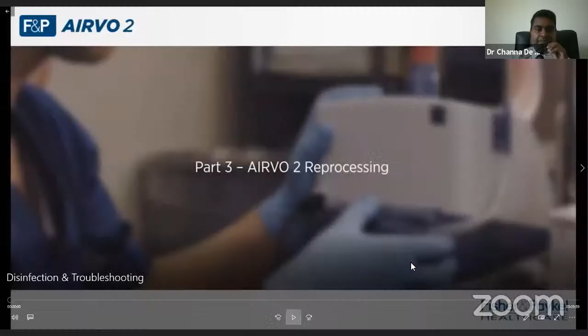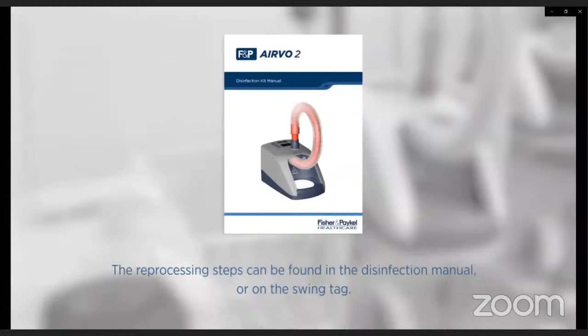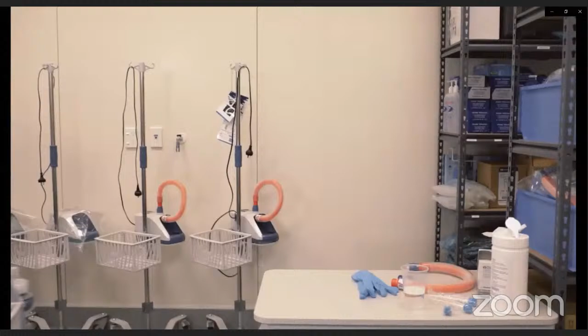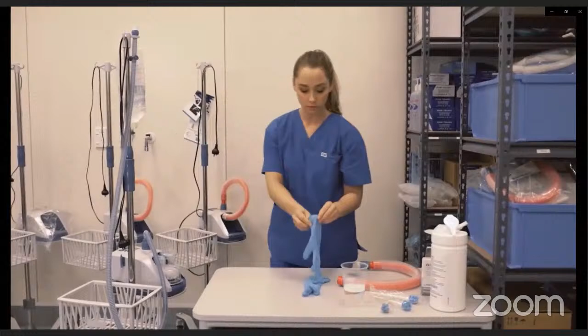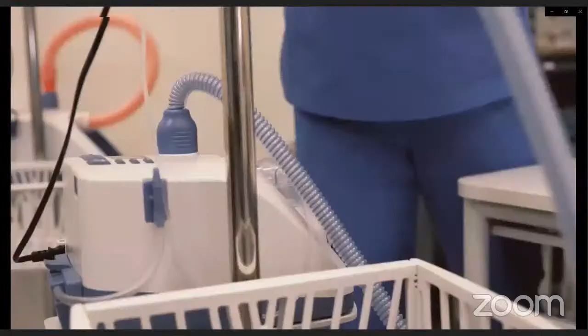The AIRVO 2 must be cleaned and disinfected between patients. This should take place as soon as possible after use. The reprocessing steps can be found in the disinfection manual or on the swing tag. These steps must be carried out between patients: cleaning, high-level disinfection, and storage. Cleaning is particularly important. You need to remove debris so that disinfection works effectively. It's easiest if you leave the AIRVO 2 on the mobile pole stand.